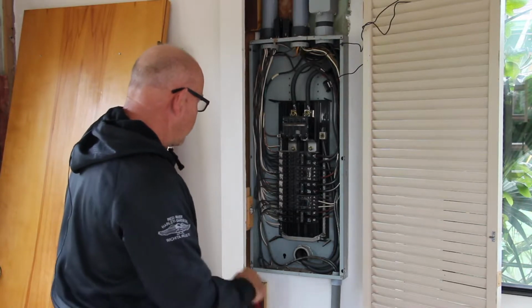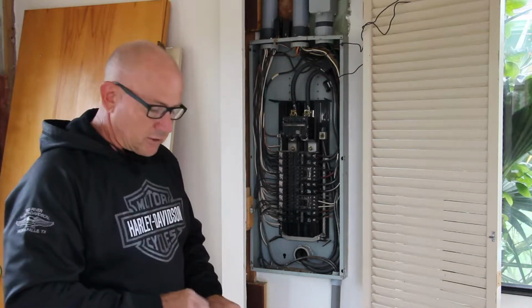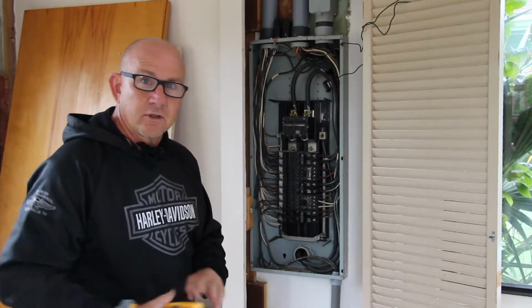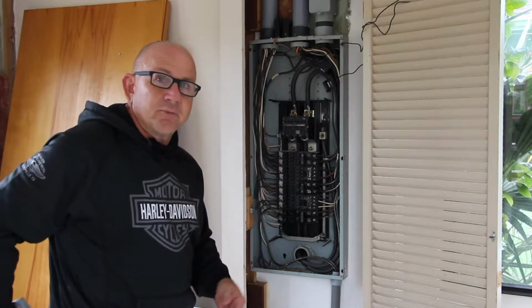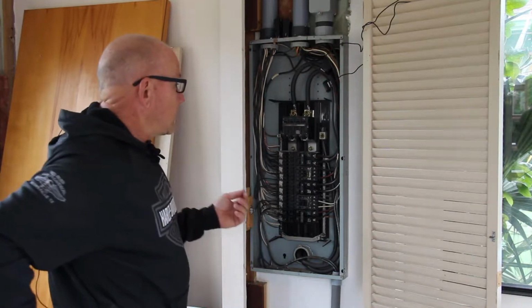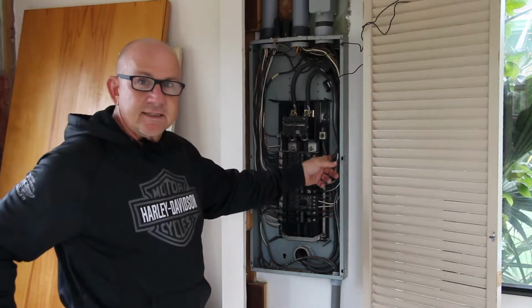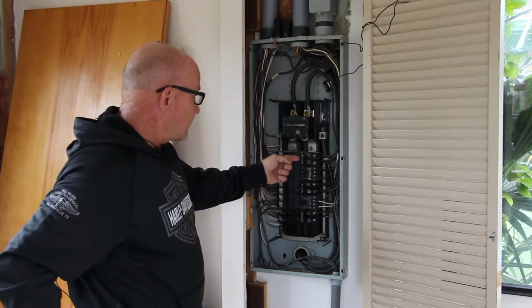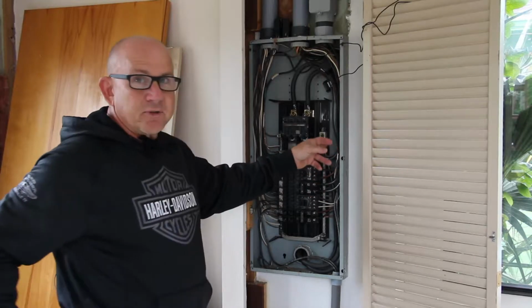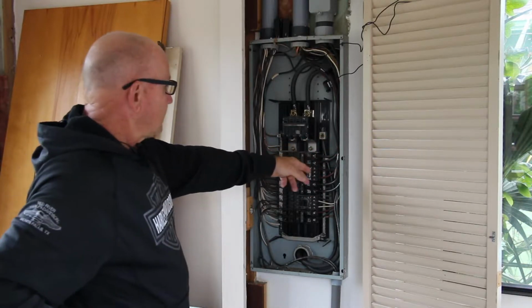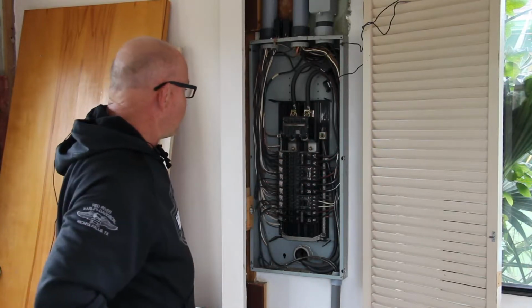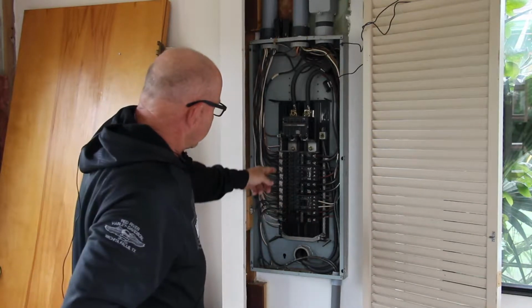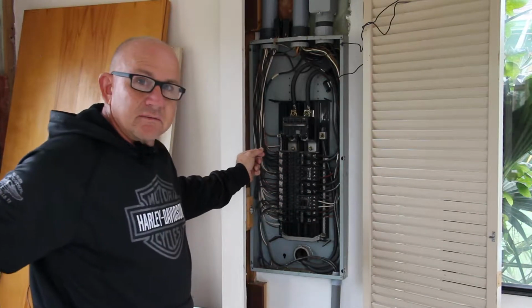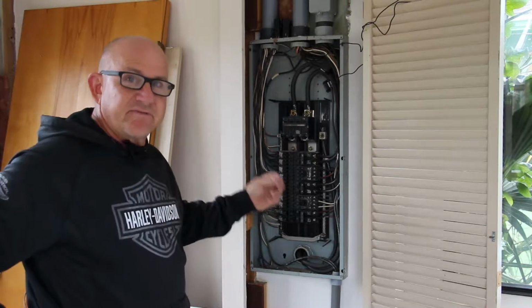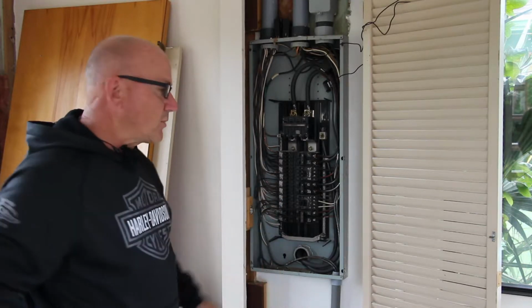We want to identify the wiring type, whether it's solid core aluminum, stranded aluminum, or solid copper. We want to be checking the wire sizing on some of the breakers. This is a 60 amp breaker. Looks like a number 6 wire that's probably going to the stove. The 20 amp breakers should be a number 12. 15 amp breakers are usually a number 14 wire.